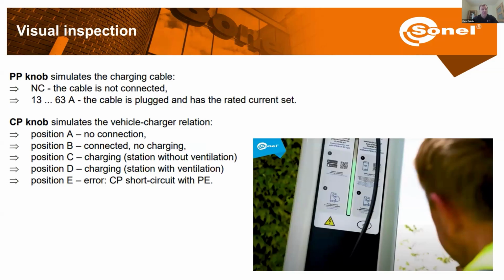And further on we're going to check different states to make sure that the communication is correct. So we're going to put our meters into different positions, simulating the car. When there is no connection, that's state A. Connected but without charging, that's position B. Then C or D simulates charging, C or D depending on whether the station is with or without ventilation. And position E simulates error. As we put our meter through all of these different positions on the control pilot, we need to check the reaction of our charging station, because they have different screens or different indicators. So we want to make sure that they work correctly.